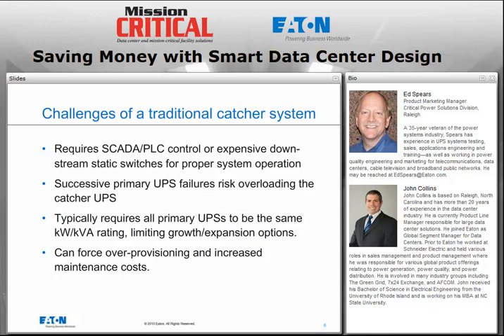It did require some type of PLC or SCADA control, and in many cases was used, albeit successfully, with some downstream static switches for proper system operation and proper system switching when problems occurred. But that again increased the complexity, and the whole idea here is to try to do this kind of thing with a minimum of complexity, especially for the operator who has to understand what they're doing and what happens anytime they take an action on site.